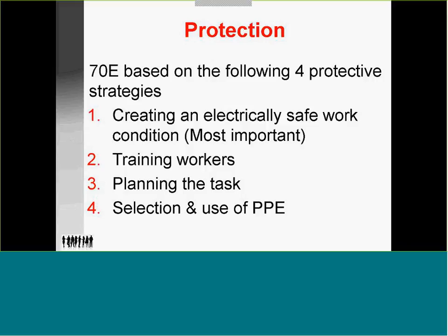Trained, which is very important. Task is important. Selection and use of PPE, and this is where there's always an issue. Clients you go into may not have completed an arc flash risk assessment. Without that, it's very difficult to determine PPE. In code, if it cannot be determined, you have to go to a Category 4 suit, which is one of the heaviest.